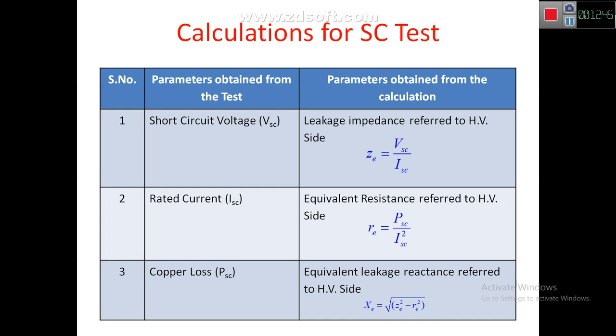Using three meters we obtain VSC, ISC, and PSC from the test. From these we calculate: the leakage impedance referred to the HV side ZE = VSC / ISC; the equivalent resistance referred to the HV side RE = PSC / ISC² (from the copper loss formula PSC = ISC² × RE); and the leakage reactance referred to the HV side XE = √(ZE² − RE²).